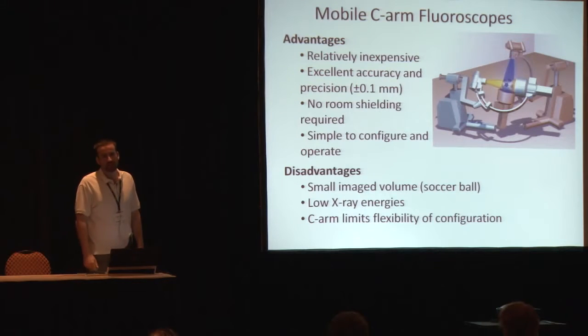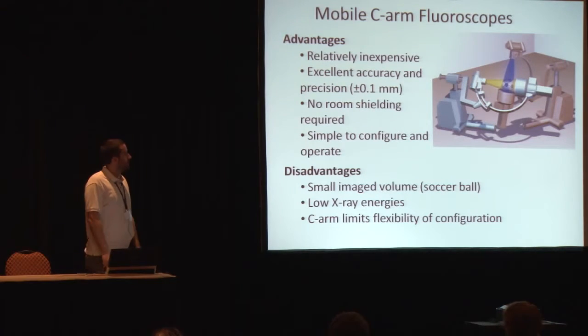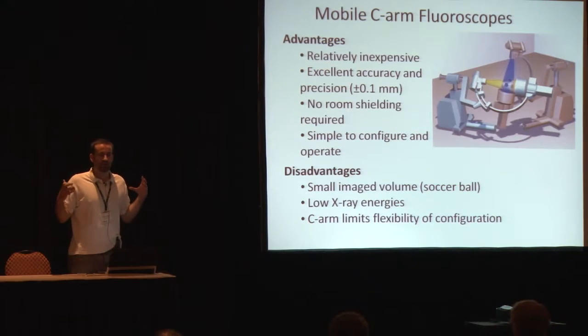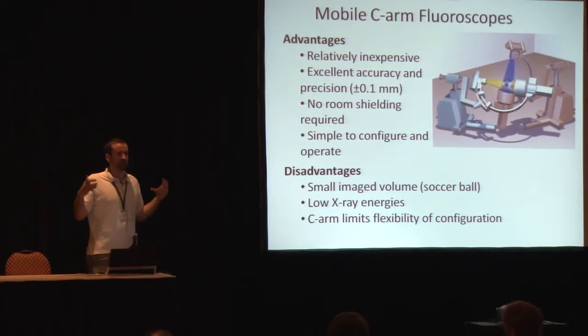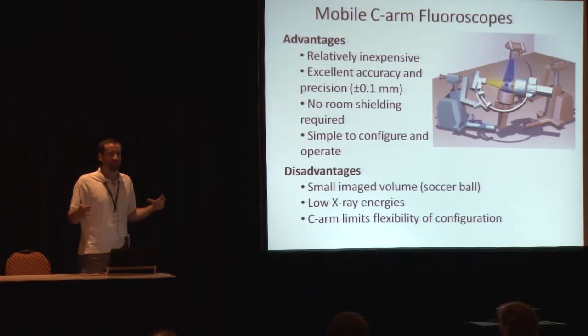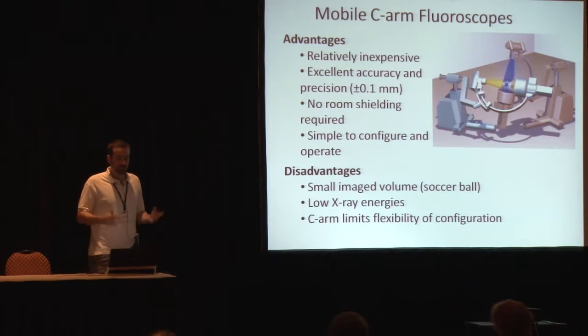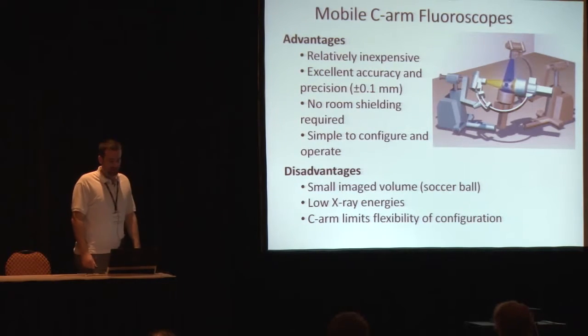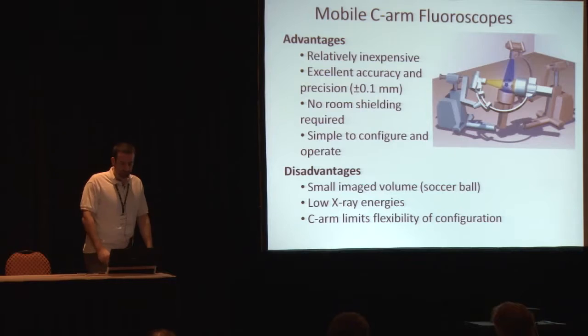So some of the benefits of this is that compared to certain systems, depending on your point of view, it's relatively inexpensive considering we're generating X-rays and getting these 3D data out. We've got very good accuracy and precision. And one of the other reasons that this system is relatively cheap is because the X-ray source and the image intensifiers are locked into position. You don't need to have a special room for this. You don't need to shield it because you're capturing all the X-rays. You get a little bit of backscatter. That's why we wear lead protection and things like that. But the room itself, cinder blocks and things like that are sufficient to shield it. And it's relatively simple to configure because it's always pointing in the right direction. Everything is kind of happy.